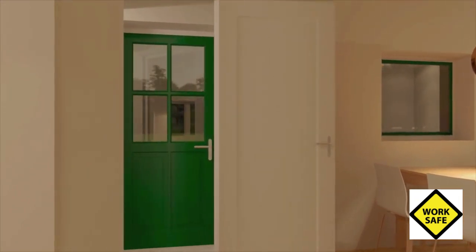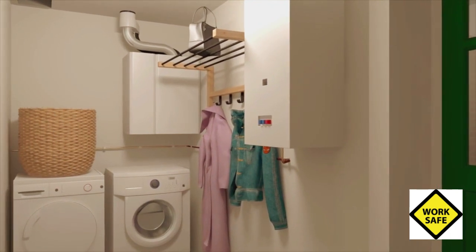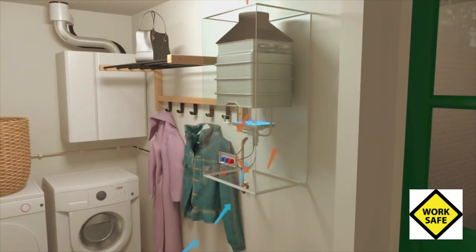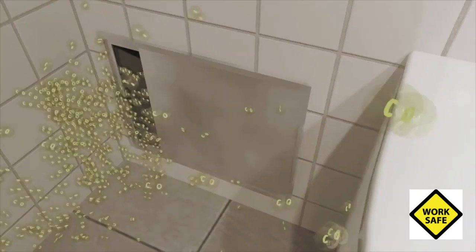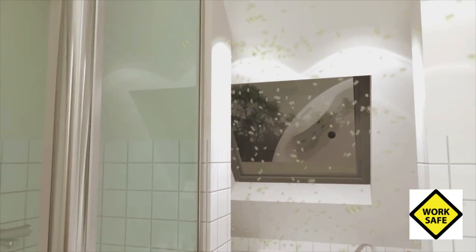In the utility room on the ground floor, a central heating boiler and gas water heater were placed. These appliances were inspected and maintained three months before the accident. The stormy wind that night disturbed the flow of fumes from the burning heater. Because the flue duct was placed incorrectly, the wind pushed the fumes back, causing air to recirculate in and around the heater. Recirculation is a common cause of carbon monoxide. The pantry filled with toxic gas. The pantry was connected to the bathroom with a laundry chute, and the ventilator in the bathroom sucked up the toxic fumes, with the fatal outcome as a result.